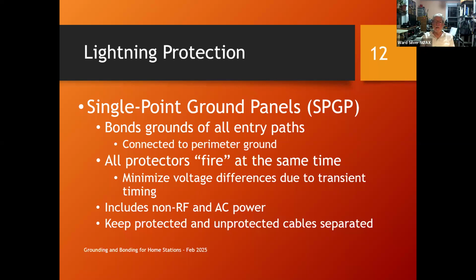Minimize the voltage differences due to the timing and keep everything going up and down together. Your single point panel should also include an AC power protector. If you can run your branch circuit over to this panel, mount a big surge protector on the panel, and then run a protected circuit over to your station.